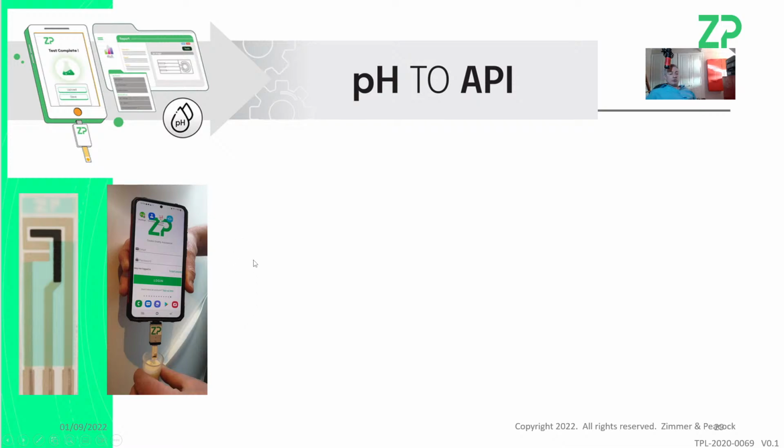This image is quite useful because it shows that electrochemical sensors, including pH sensors, really don't care about the opaqueness of the sample. It was just for illustration, for a different reason, but we're sticking the sensor in milk here. If you've got a non-transparent, coloured, dirty sample, for example, blood or milk, electrochemical pH sensors will still operate, unlike optical systems where you'd sometimes have to do filtering, sometimes dilution, but they require some sort of sample prep.